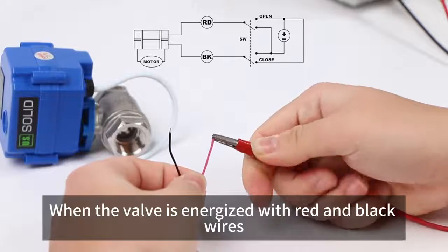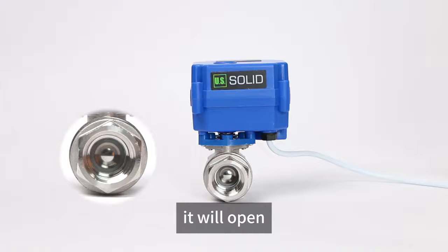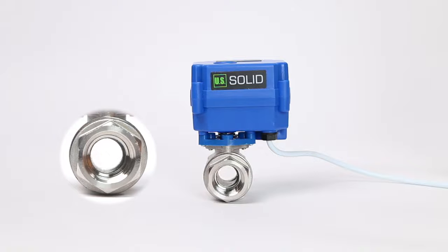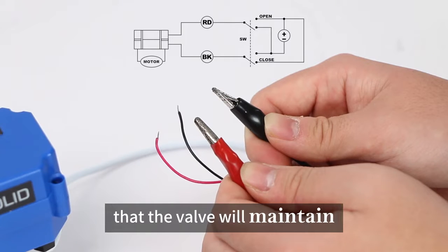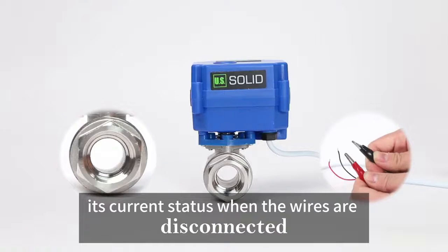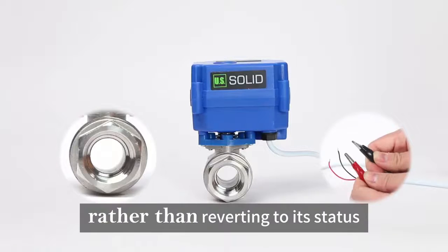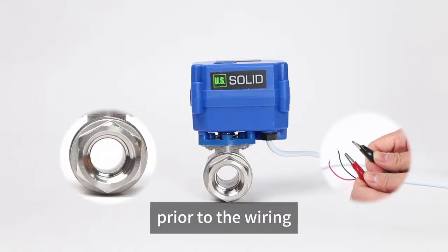When the valve is energized with red and black wires, it will open. Please keep in mind that the valve will maintain its current status when the wires are disconnected, rather than reverting to its status prior to the wiring.